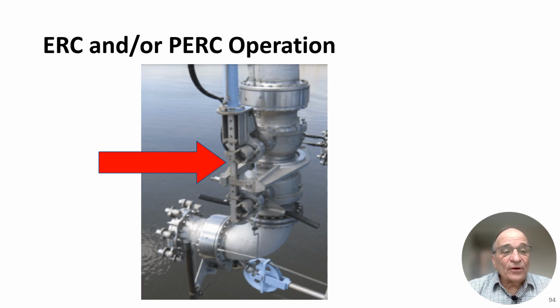I earlier mentioned an ERC or PERC. That's emergency release coupling or powered emergency release coupling. And what it is is two ball valves as shown here, and a release coupling. In the event a ship drifts off the berth and you're loading or unloading a ship, you want this to break away rather than rip the arms off of the berth. So if the ship moves too far of a distance away from the berth, or if an emergency release coupling button is pressed, this will activate. These two ball valves will shut, and as soon as they shut, this release coupling will release this section from the rest of the loading arm.